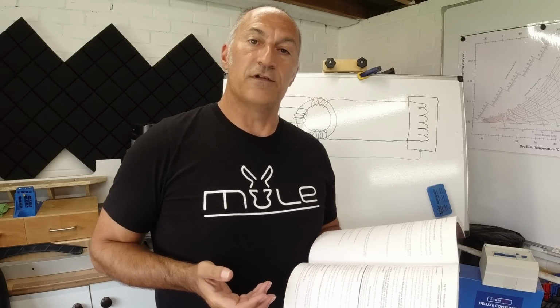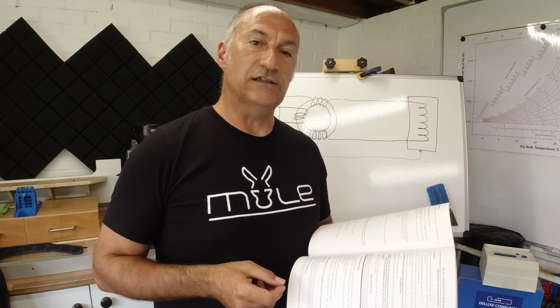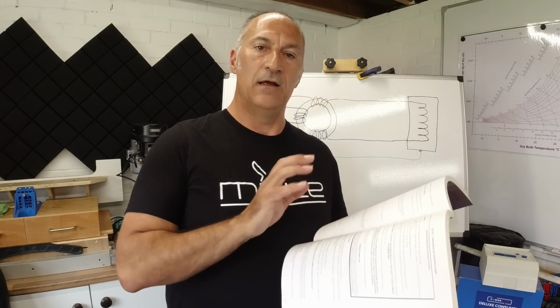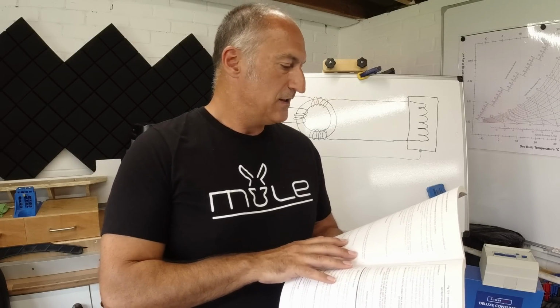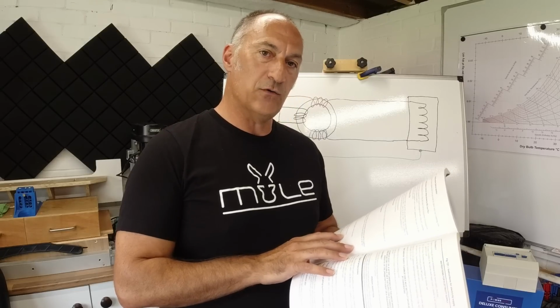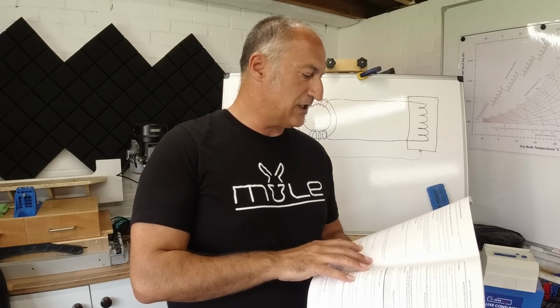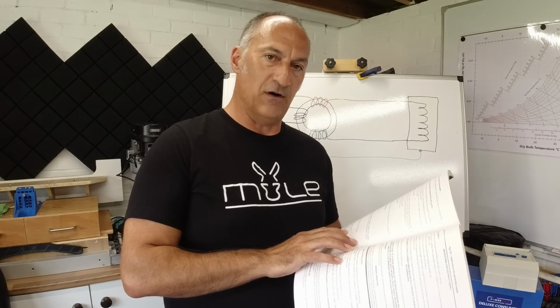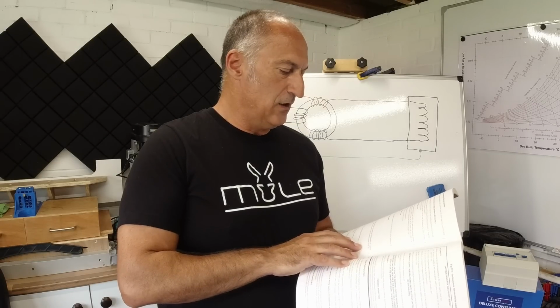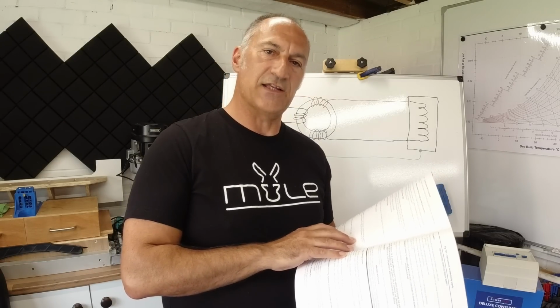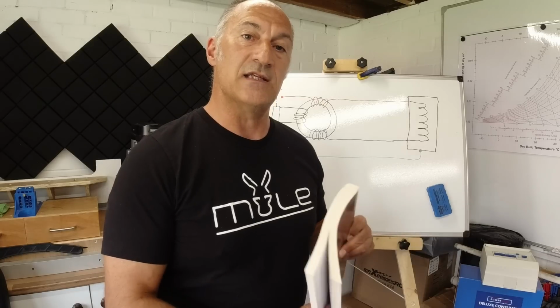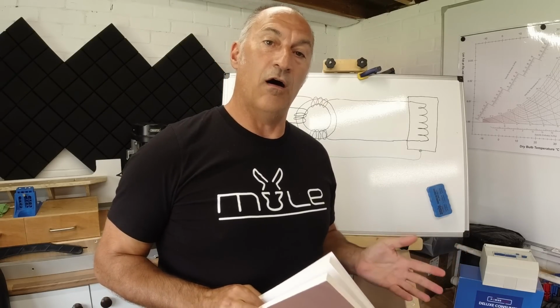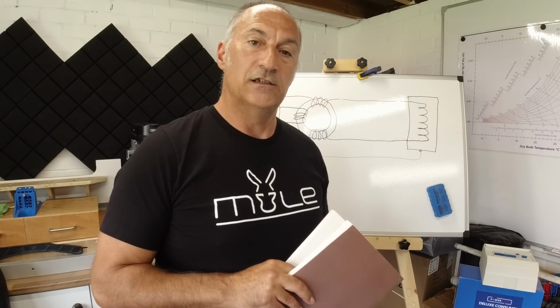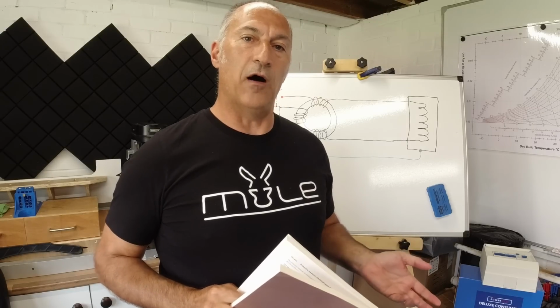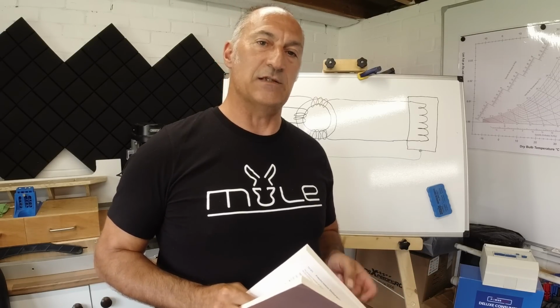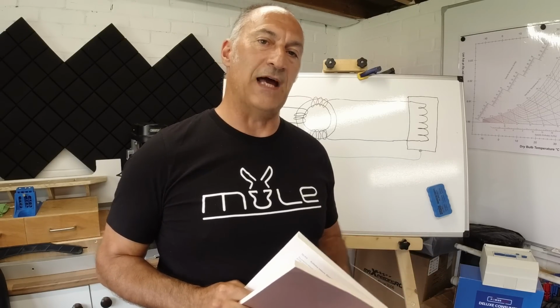Now there are a few different types of MCBs on the market, so what do we need in our campervan to comply with the regulations? Well, section 721 states on final circuits, each final circuit shall be protected by an overcurrent protective device, MCB in our case, which disconnects all the live conductors of that circuit. So basically what that means is the line and the neutral are considered to be live conductors. So our MCB needs to be a double pole MCB. It needs to be able to disconnect both the line and the neutral of that circuit.